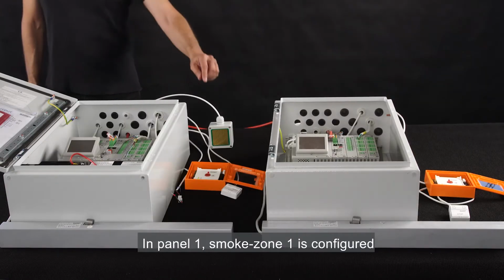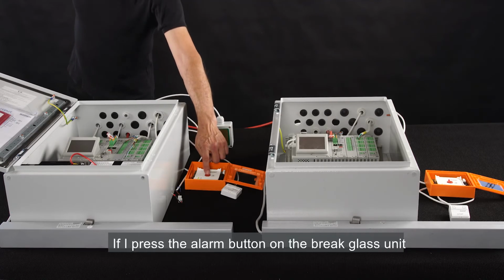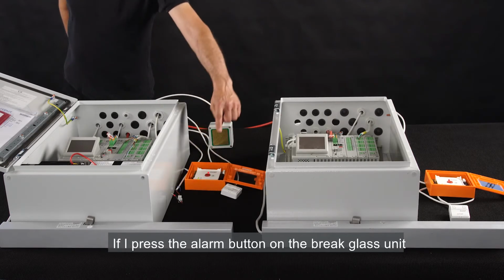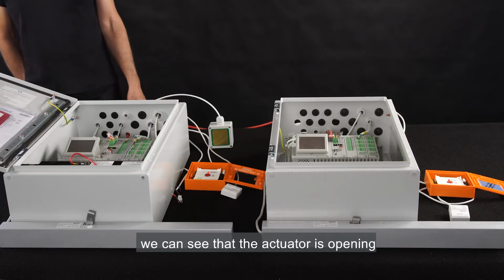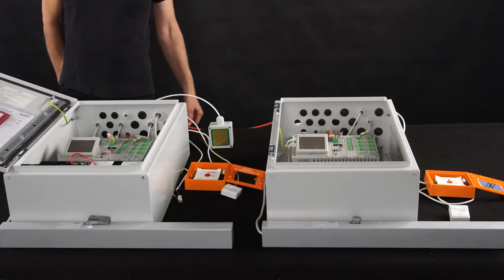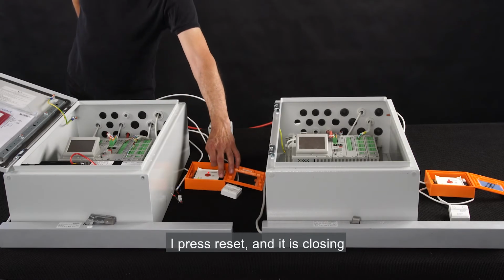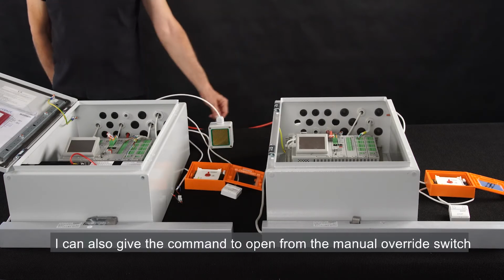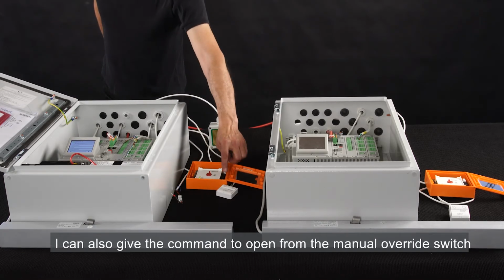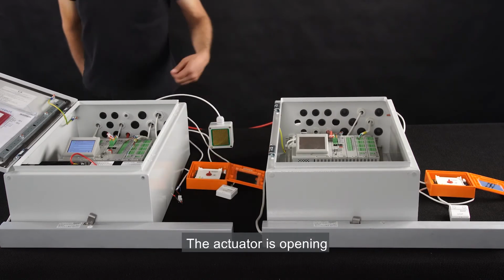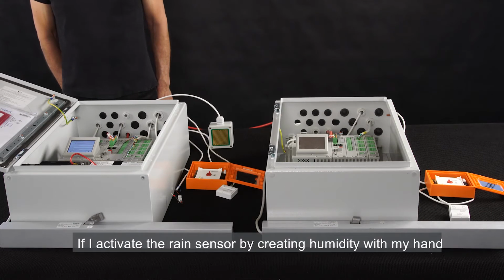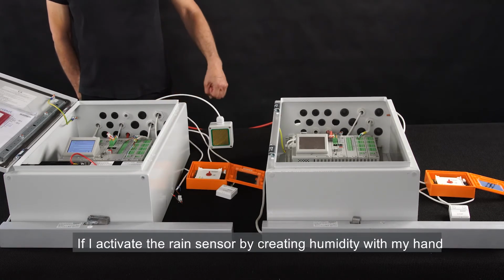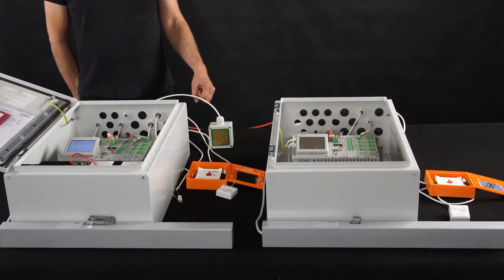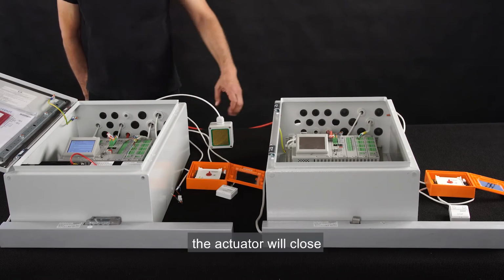In panel 1, smoke zone 1 is configured. If I press the alarm button on the break glass unit, we can see that the actuator is opening. I press reset and it closes. I can also give the command to open from the manual override switch. The actuator is opening. If I activate the rain sensor by creating humidity with my hand, the actuator will close.